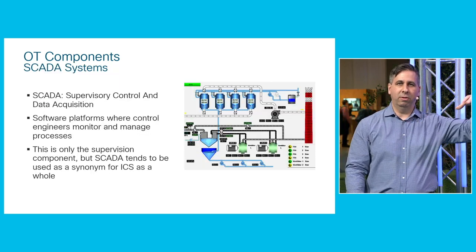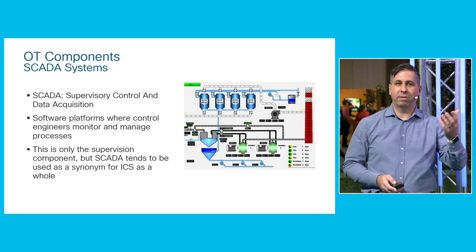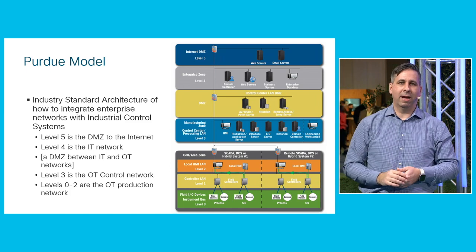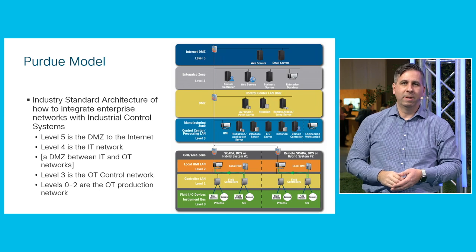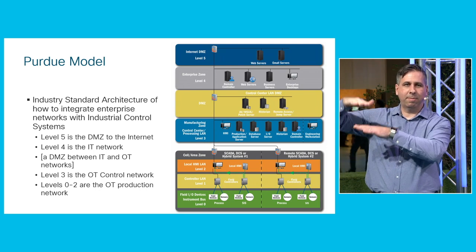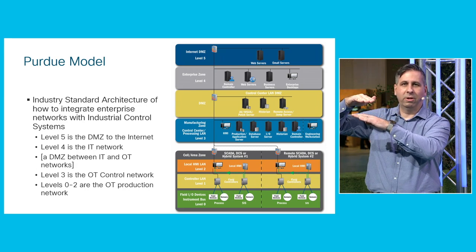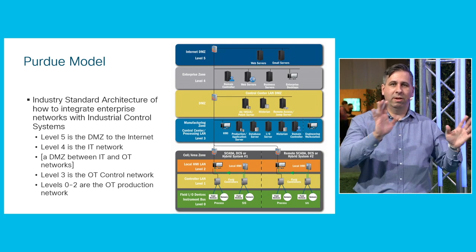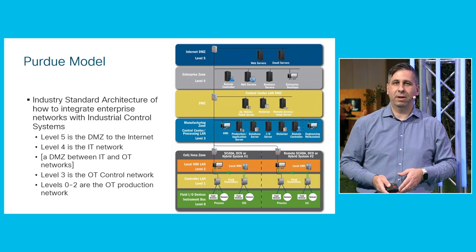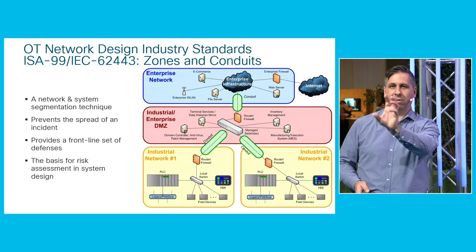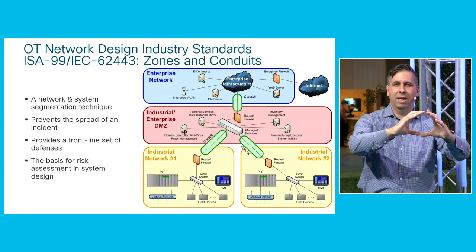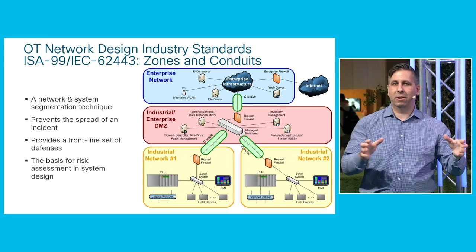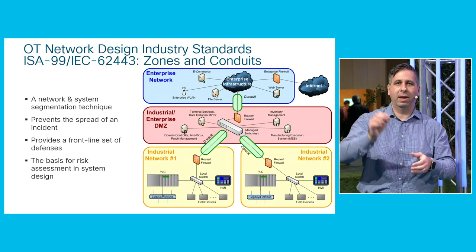Groups of PLCs are then supervised by SCADA systems — supervisory control and data acquisition systems — which are integrated with the broader enterprise network using the traditional Purdue model. There are lots of hierarchy and separation requirements. You want a complete demilitarized zone not only between the company and the internet, but even between the IT part of the company and the production OT level, to restrict communication and maintain security.